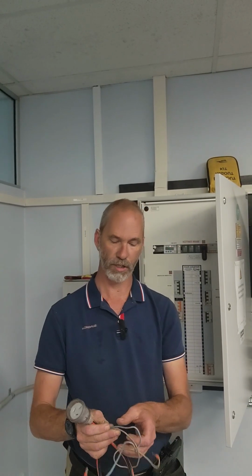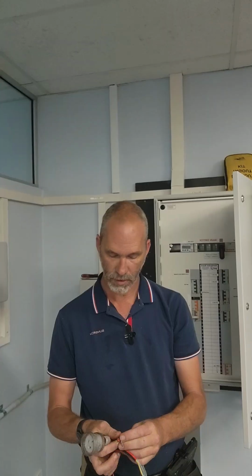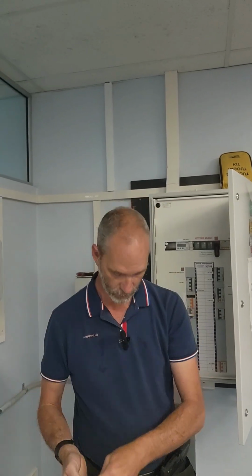So in the past when I've been doing these tests, I've just used the end of an extension lead where I've just stripped out the end of the cables. I got fancy, put some bootlaces on the ends. Neutral, active, heater, hairdryer, a load. And basically all I'm doing is just checking. I've got no generation, so I'm talking pure load. And I'm just checking that my A is A, B is B, C is C. So if I'm getting my local data and I'm saying testing A phase and I'm not seeing it go up when I apply a load to A phase, there's an issue there.